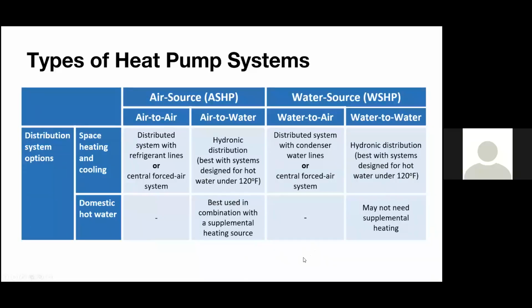And then on the water source, water to air, that's your typical water source heat pump. On one end, it's extracting or rejecting heat to a condenser water loop. On the other end, it's cooling or heating air. And you might know those are water source heat pumps inside a condo suite that a lot of people have, or in an office building. You have distributed water source heat pumps, and they're all connected to a condenser water line. And then a water-to-water heat pump, those are more common if you're using a geothermal system. We've actually worked on a few school jobs that use water-to-water chillers that essentially reject or inject the heat from a geothermal loop.